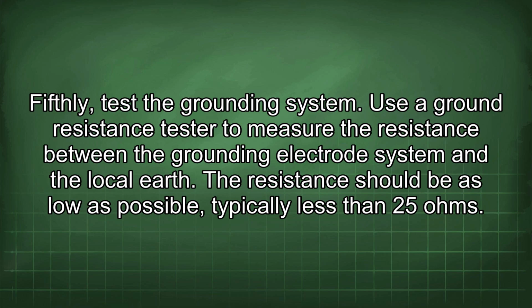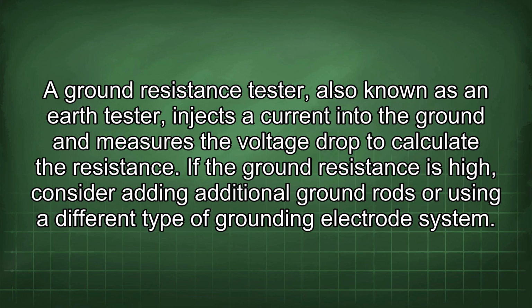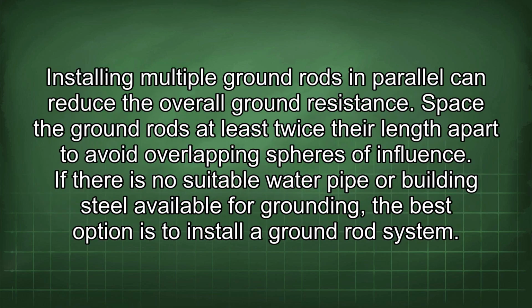Use the ground resistance tester to measure the resistance between the grounding electrode system and the local earth. The resistance should be as low as possible, typically less than 25 ohms. A ground resistance tester, also known as an earth tester, injects a current into the ground and measures the voltage drop to calculate the resistance. If the ground resistance is high, consider adding additional ground rods or using a different type of grounding electrode system. Installing multiple ground rods in parallel can reduce the overall ground resistance.